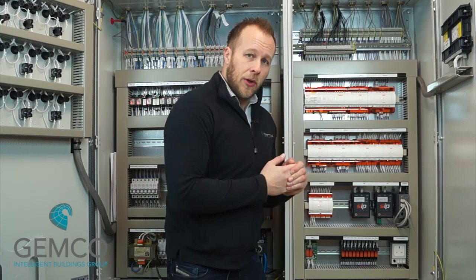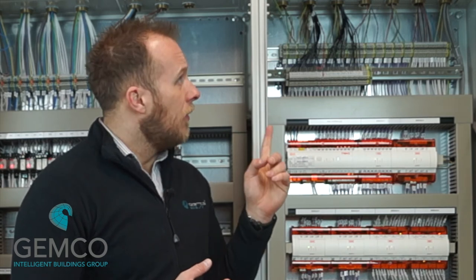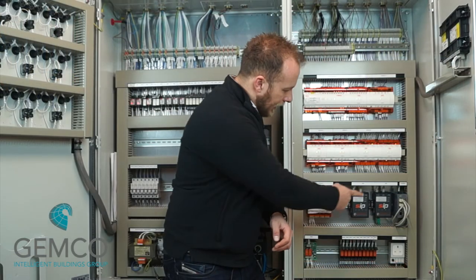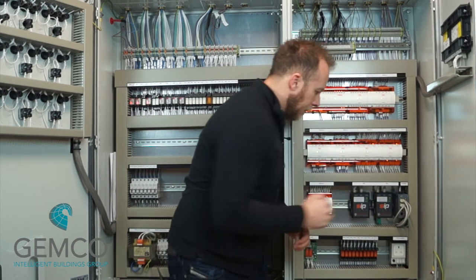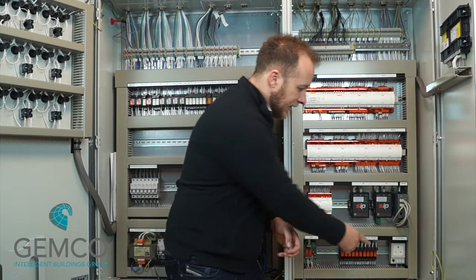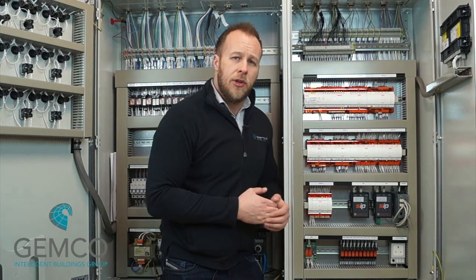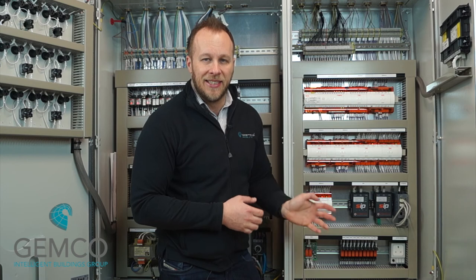This is a web-based controller. It's able to be linked into your network. If you were to provide an Ethernet point up there, you could just plug it in and you'd be able to pull up a web page that will give you all of this, the display and the settings and all the temperature values and everything we can access through the IQV8. All right, and then down here we've got an Ethernet switch where you can plug in that network cable. And then there's a socket down in the bottom right hand corner. That socket should only be used for an engineer's laptop only. You mustn't plug in things like lights, transformers or anything else into that socket.